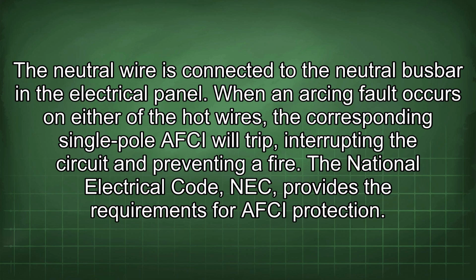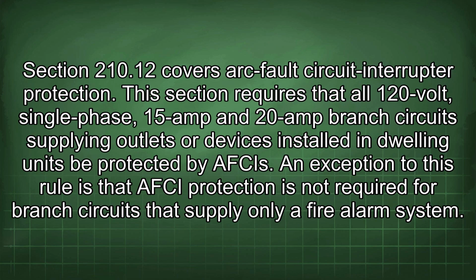and preventing a fire. The National Electrical Code, NEC, provides the requirements for AFCI protection. Section 210.12 covers arc fault circuit interrupter protection. This section requires that all 120-volt, single-phase, 15-amp and 20-amp branch circuits supplying outlets or devices installed in dwelling units be protected by AFCIs. An exception to this rule is that AFCI protection is not required for branch circuits that supply only a fire alarm system.